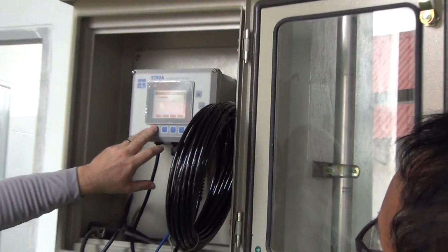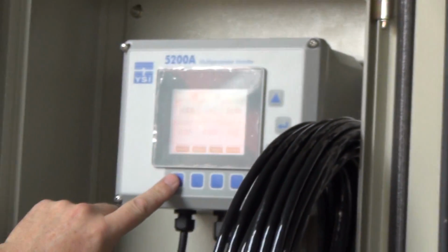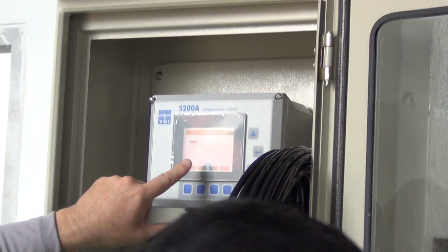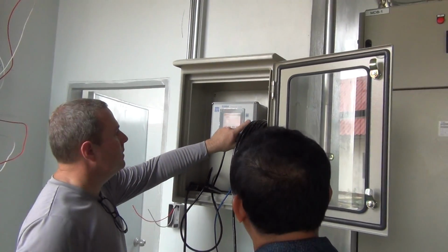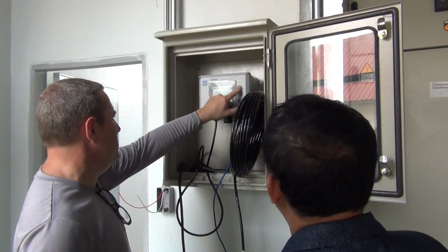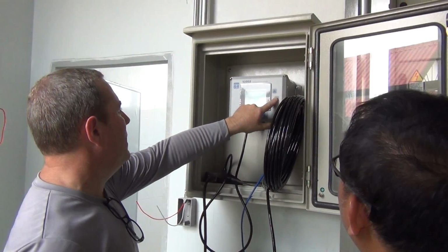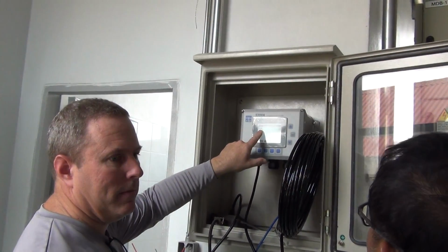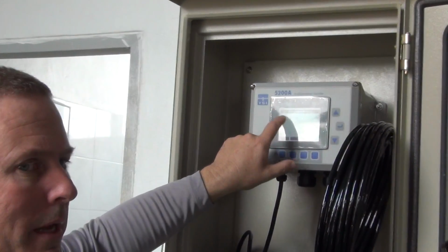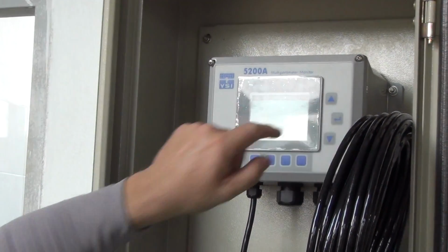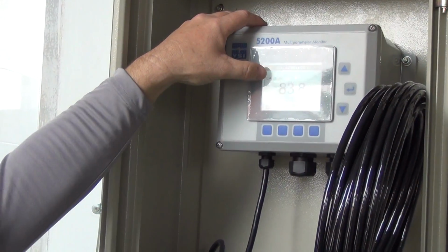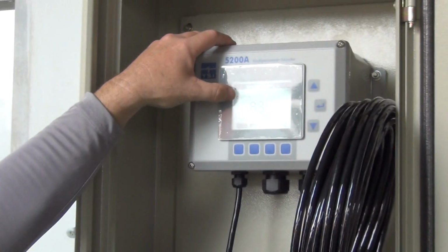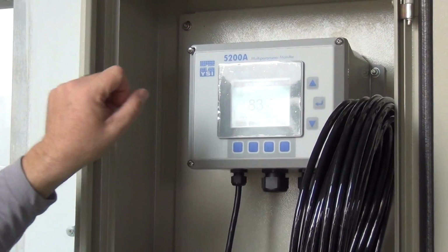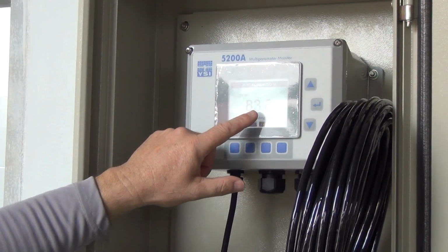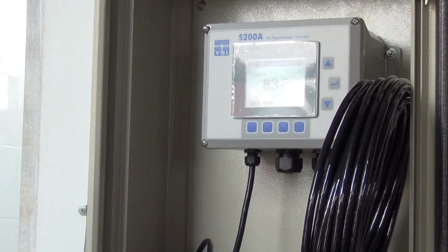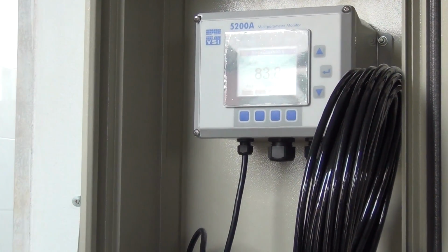So I'm going to go to here. I'm going to press menu. I'm going to press calibration. I'm going to choose DO. I'm going to select saturation. You can do milligram per liter or saturation. I press saturation. At this altitude, under these conditions, it should read 100%. It's currently reading 83.8%, and so we know that it's out of calibration.